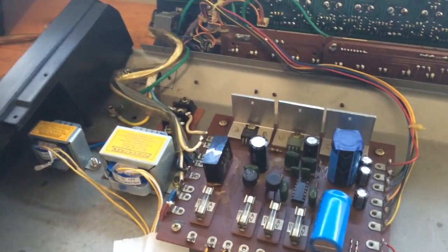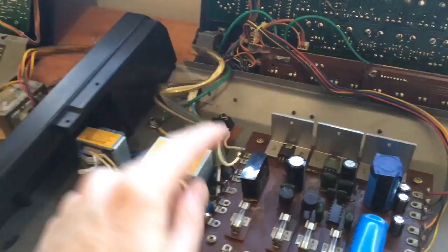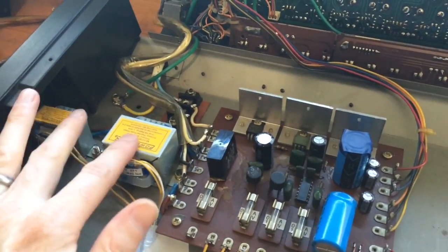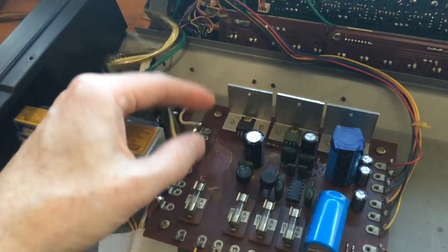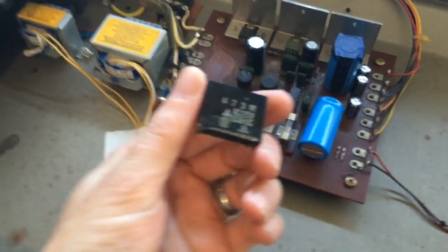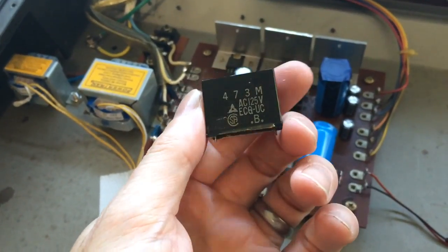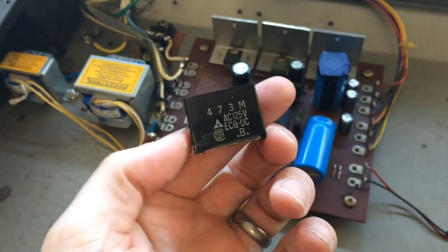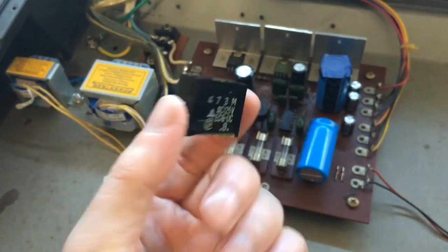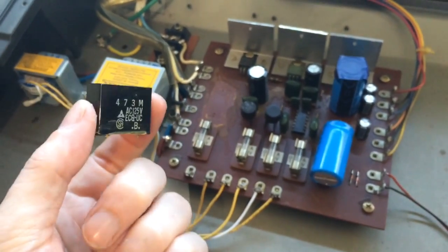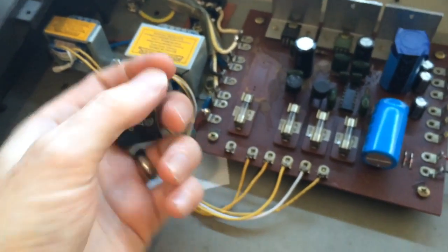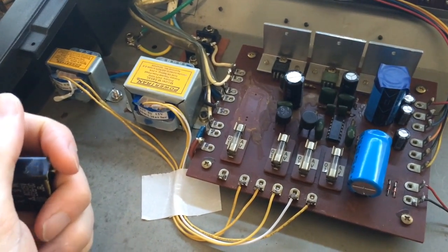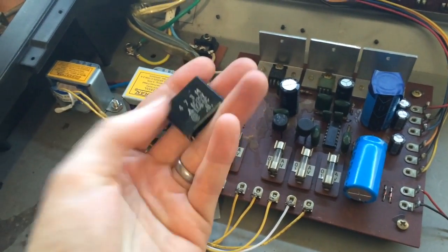So the capacitor that was in here was 110 volt rated, and now I've changed it to 240, I've had to pull it out. So this is 125 volt rated and that would have blown up if I plugged it into 240. Now it doesn't affect the operation of the instrument. It's across the mains and it's to stop high frequencies getting back out.